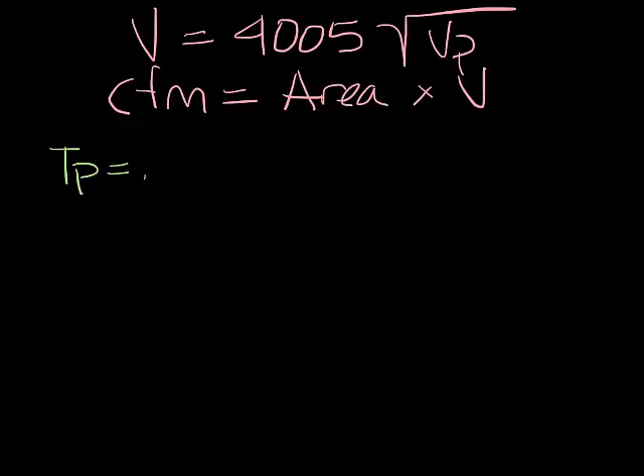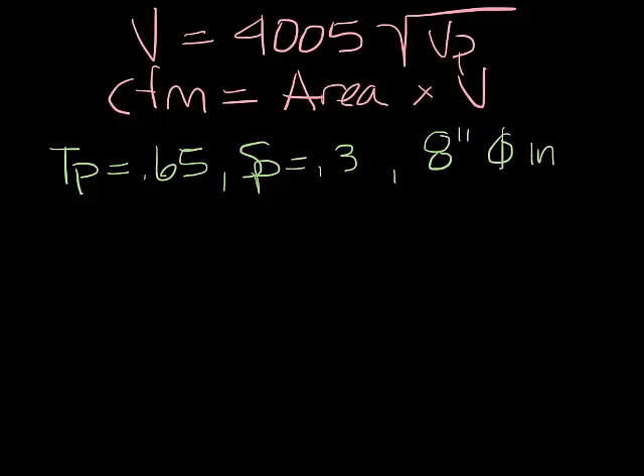So now let's look at an example. Let's say you measure a total pressure of 0.65, a static pressure of 0.3, and you have an 8 inch round inlet.